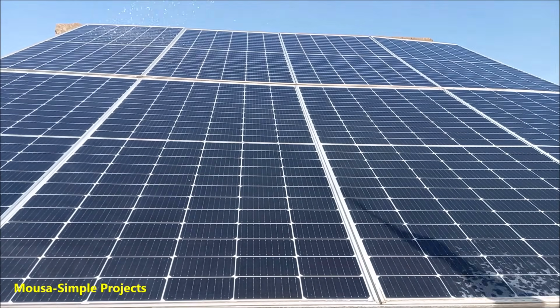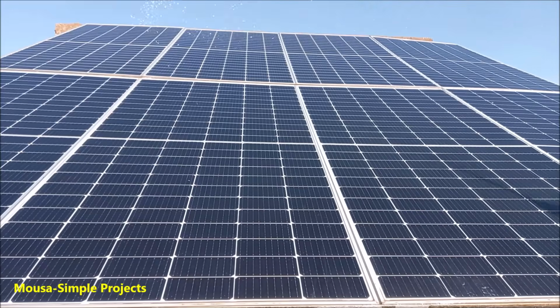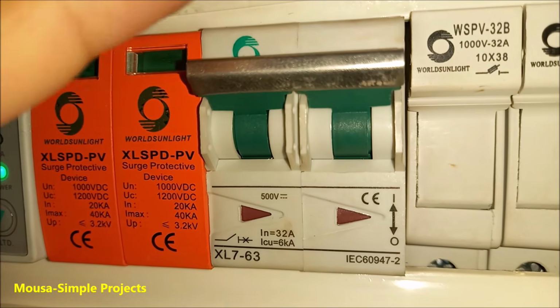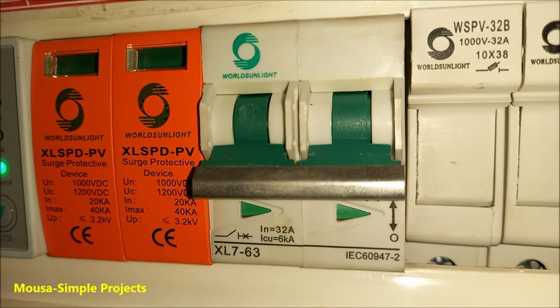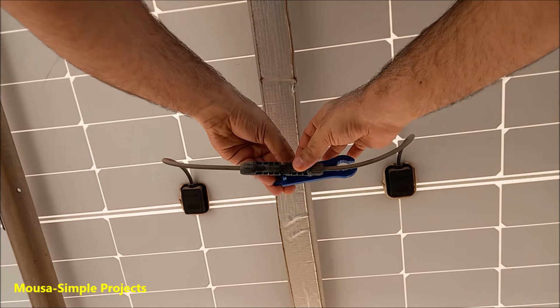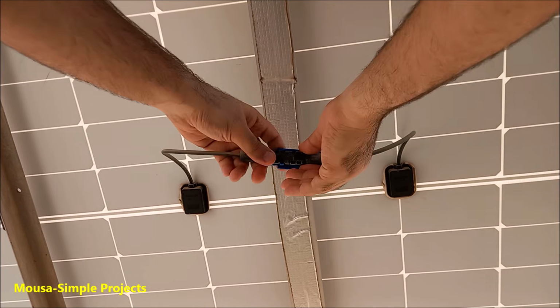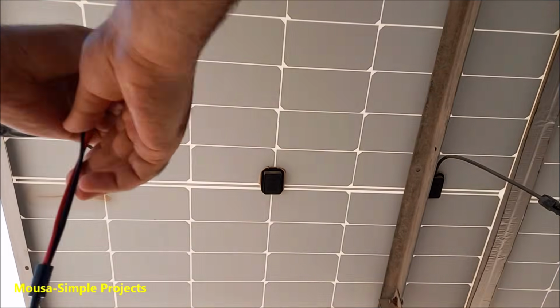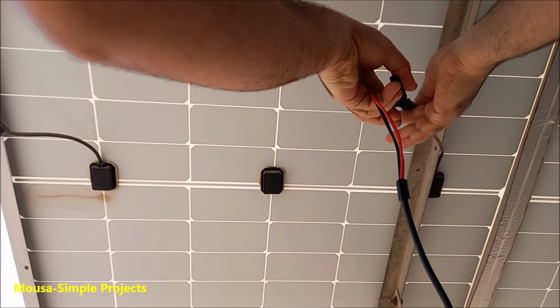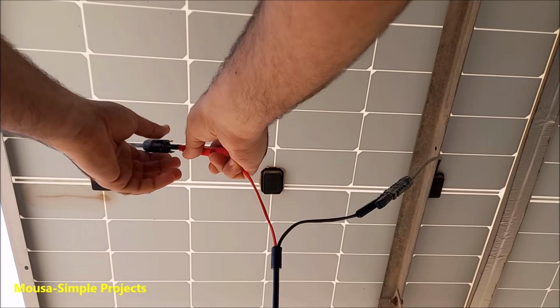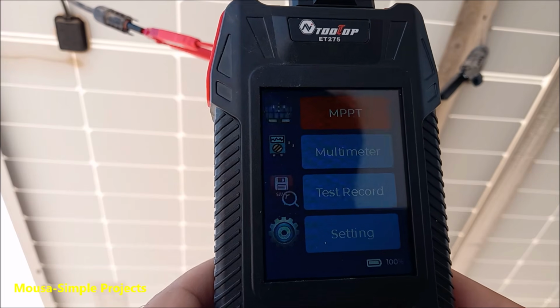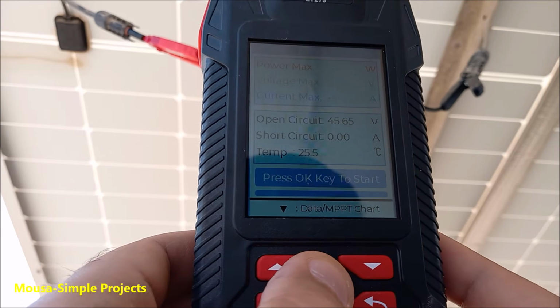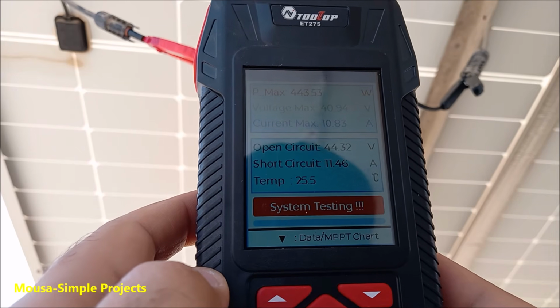I'm waiting for 12 p.m. when the sun is facing the solar panels directly. First you have to switch off the circuit breaker, because disconnecting the MC4 connector under load is so dangerous, it can arc over and catch fire. Connect the red wire to the positive terminal and the black one to the negative terminal. Select MPPT and press OK. The testing process takes 8 seconds.